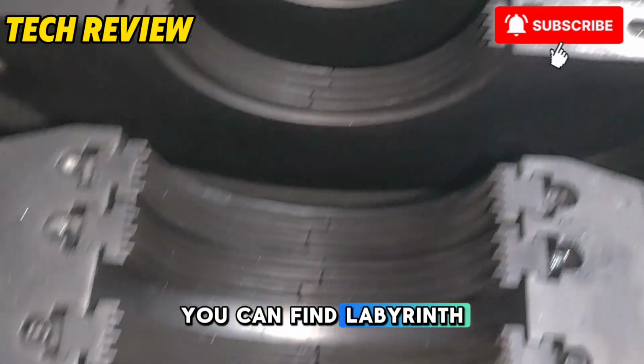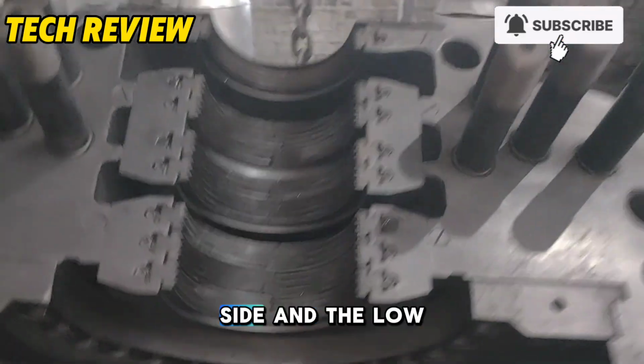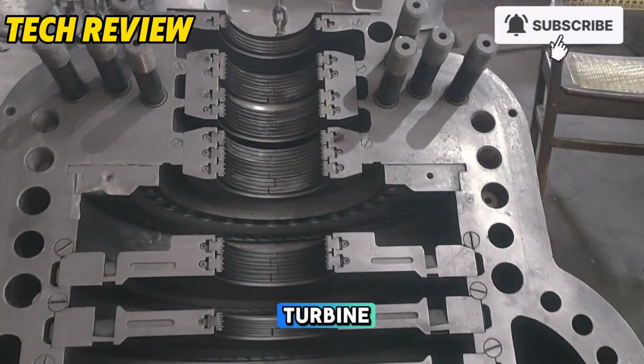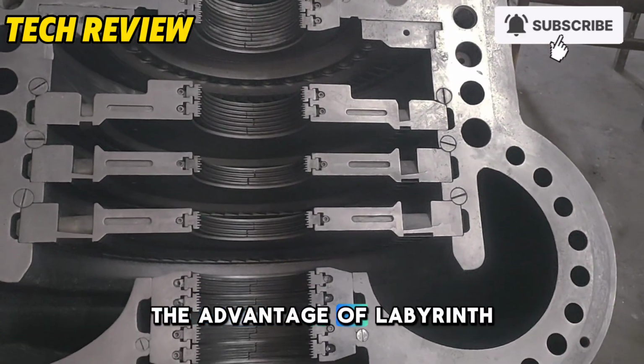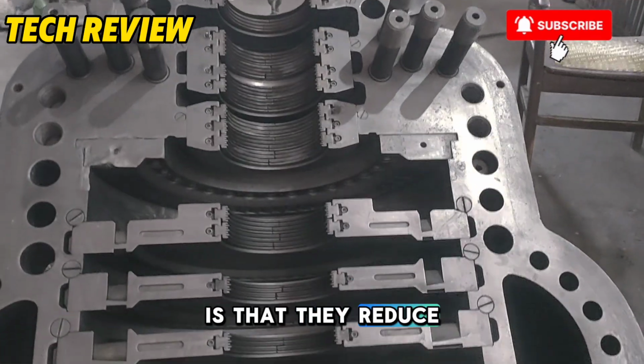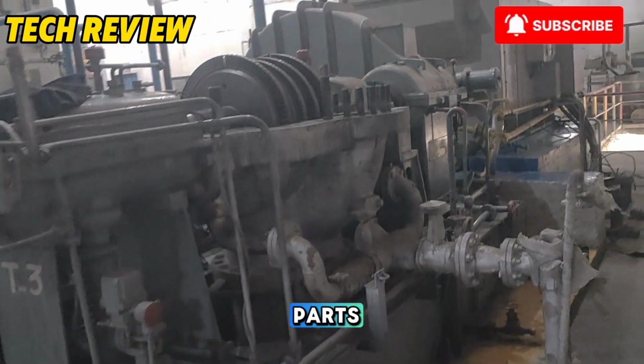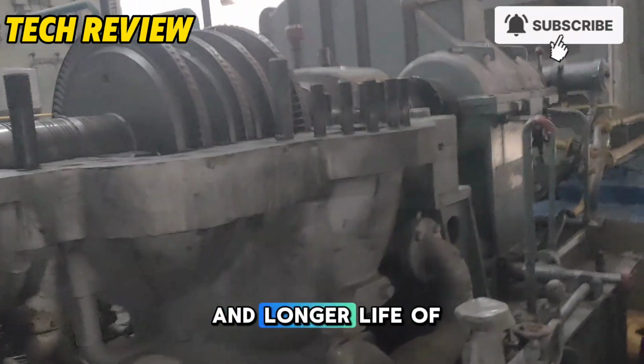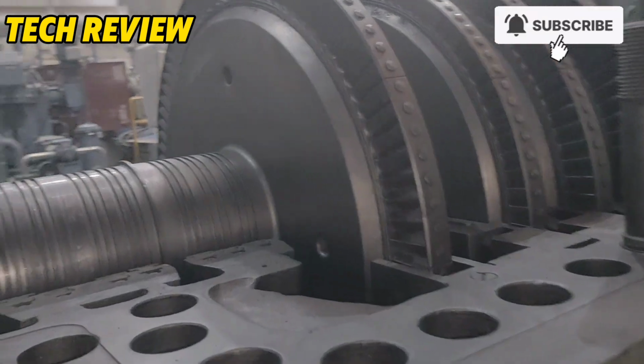You can find labyrinth seals both on the high-pressure side and the low-pressure side of the turbine. The advantage of labyrinth seals is that they reduce steam loss without physical contact between rotating and stationary parts, which means less wear and longer life of the turbine.